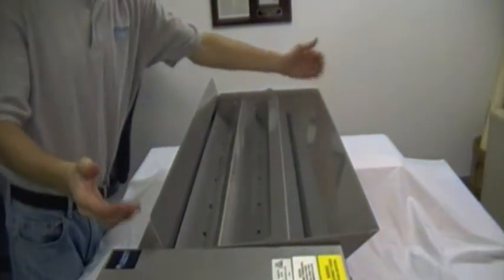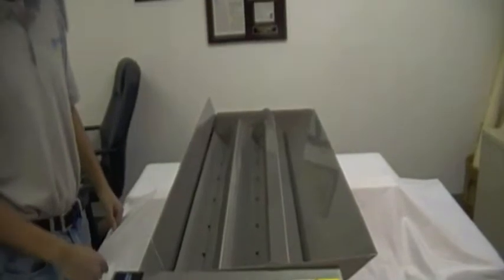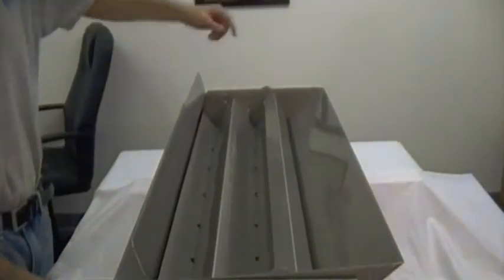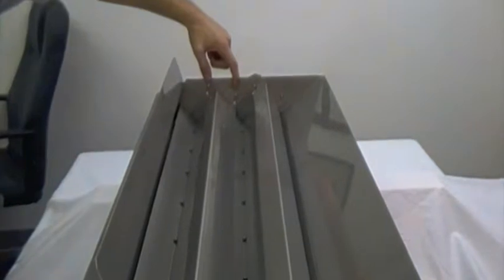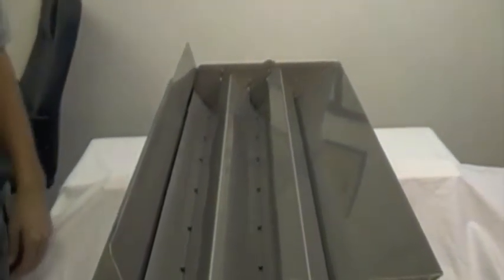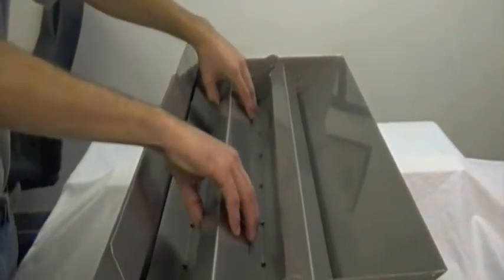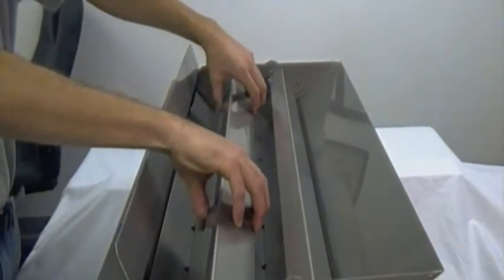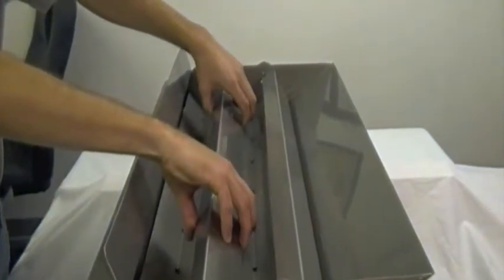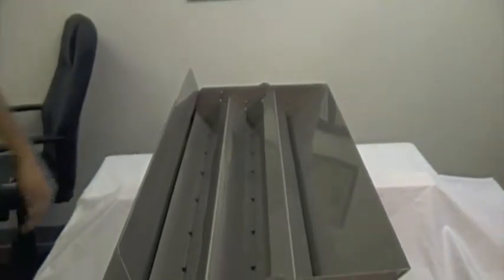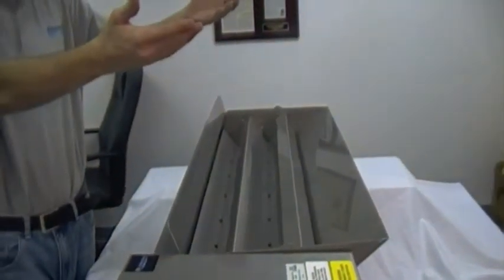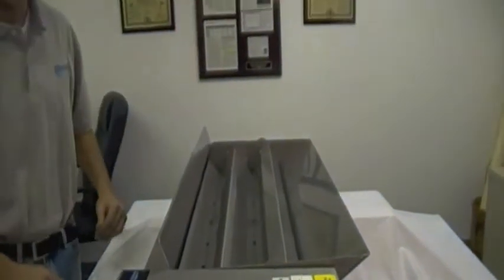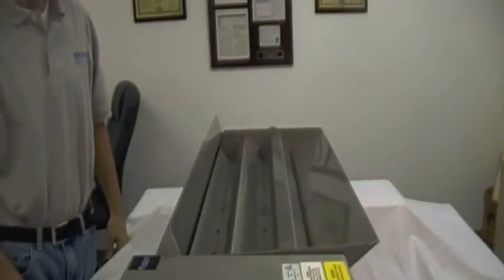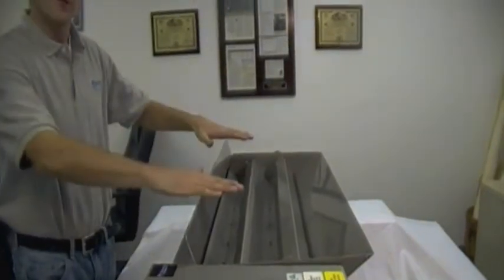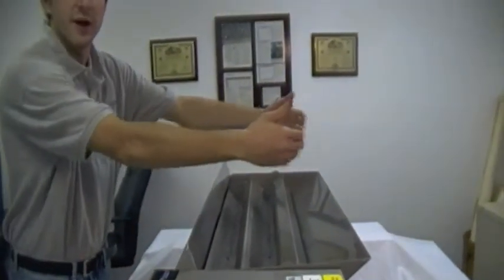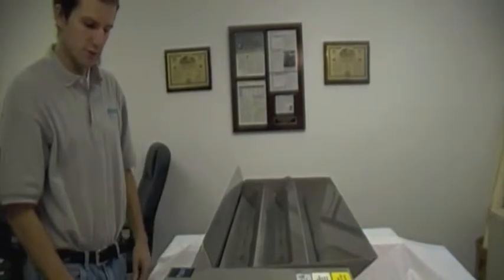The discharge baffle can be easily adjusted dependent on airspeed inside the air handler or ductwork. There are 2 screws, each with a nut, located on either side of the baffle. This allows the baffle to be tilted backwards or forward, up and down. Raising the baffle allows more airflow to increase the capacity in low airspeed situations. Likewise, lowering the baffle will prevent spitting from the humidifier in high airspeed situations.